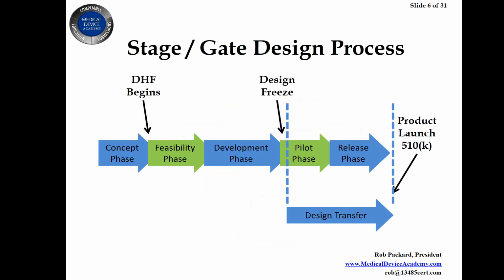But when you have a notified body or registrar looking at your design history file, they're going to want to see that design history file as well, and they're going to want to understand when you open and close it and how you maintain it.